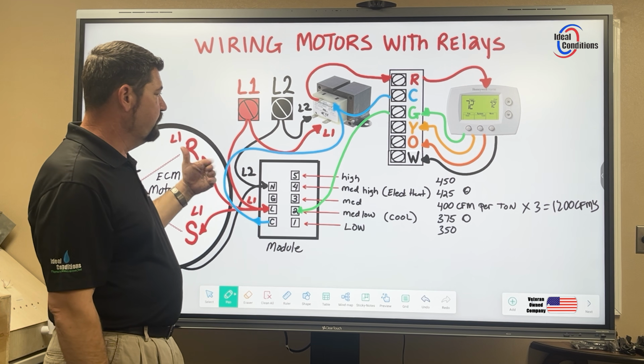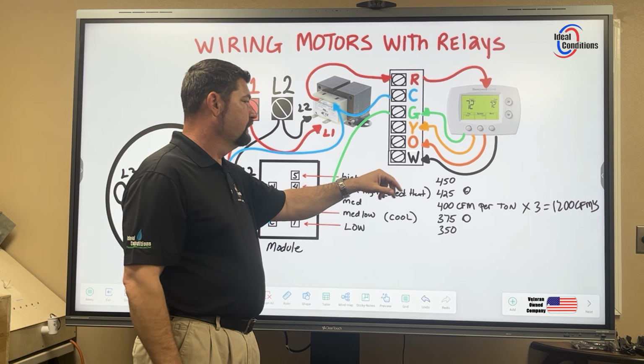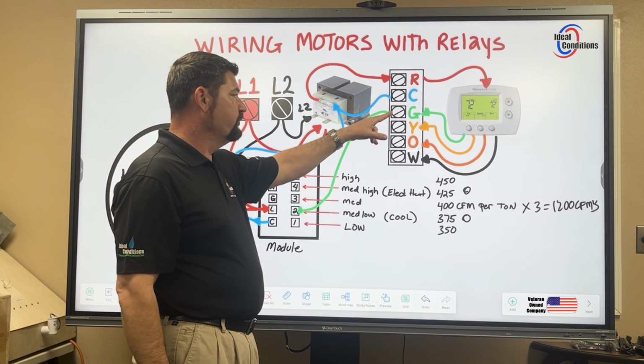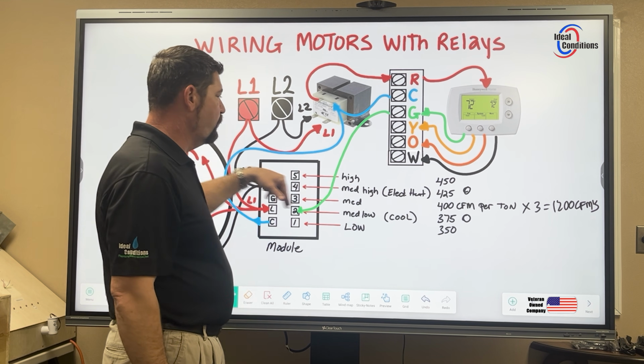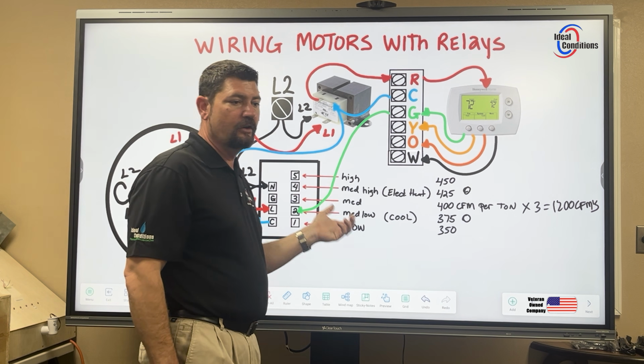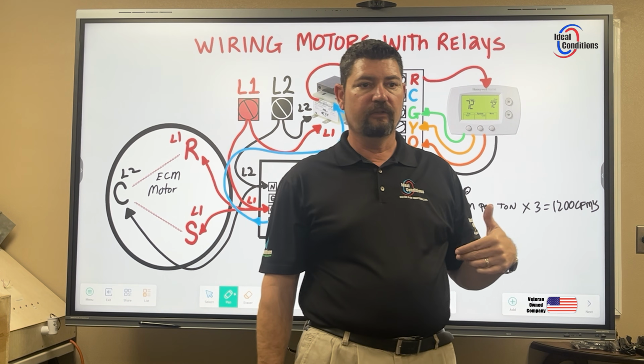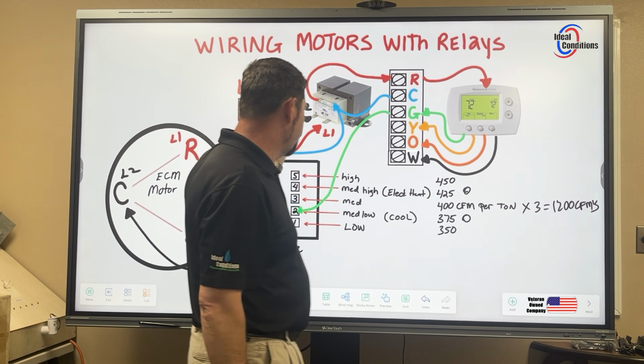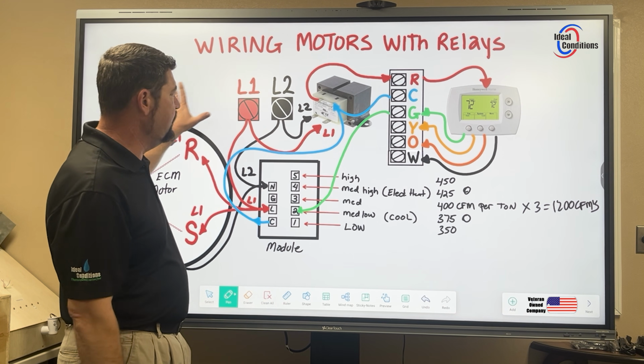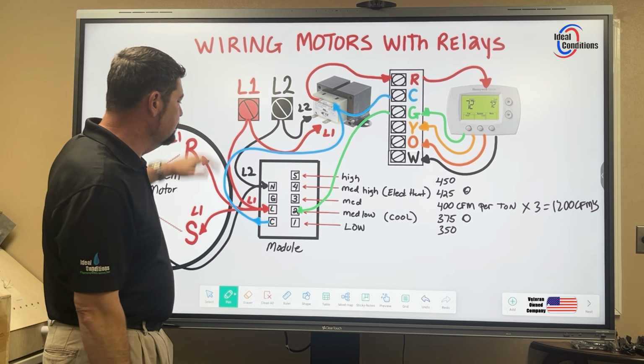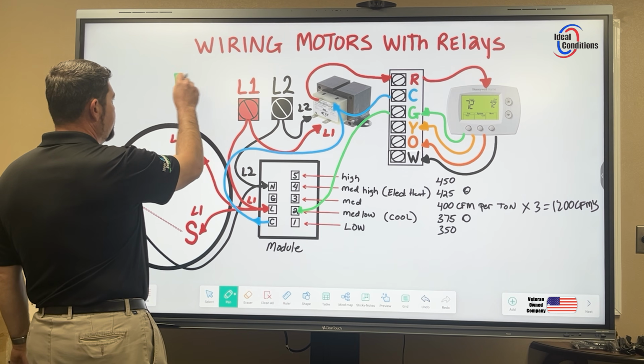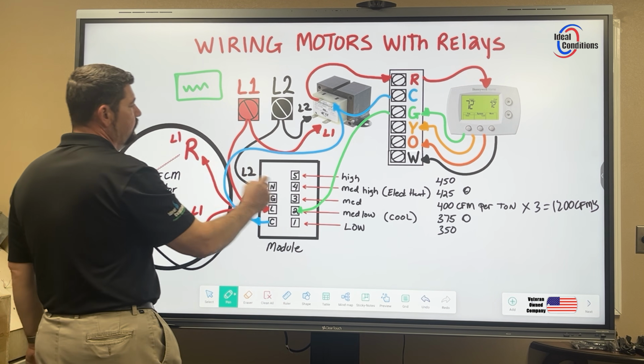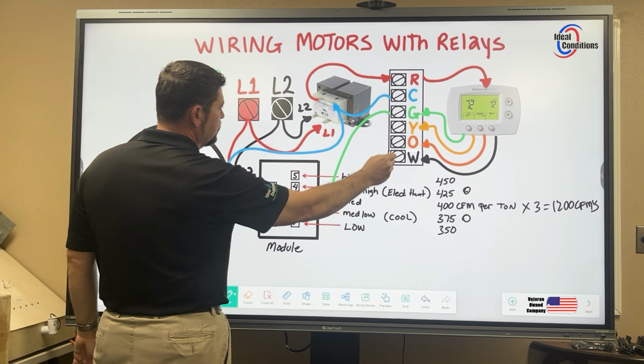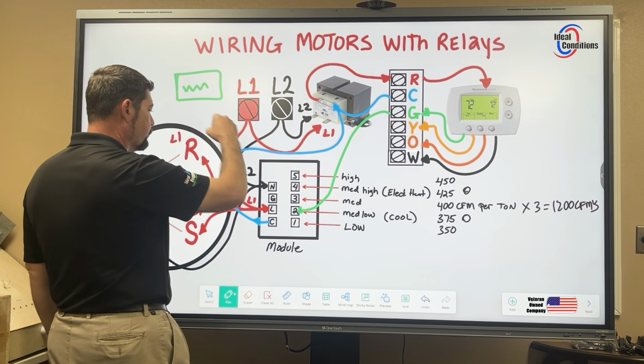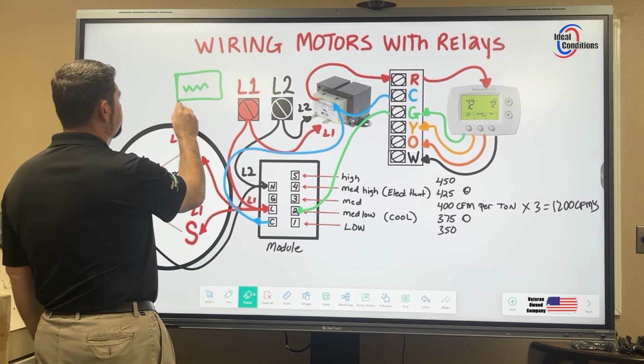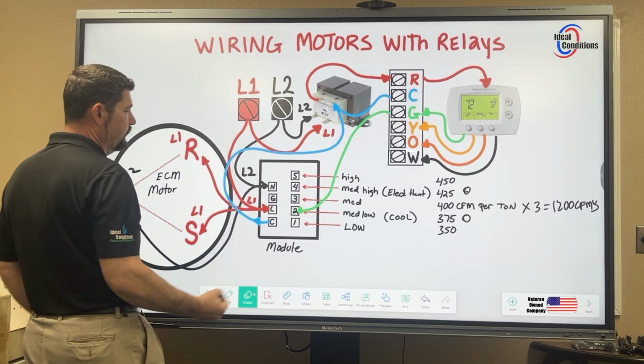So what they have done is they've actually taken the W, and if it's getting 24 volts, G's always there. They've taken that and they've wired that to your heat strips. And then also as a safety, if that relay ever sticks or if it's getting 24 volts, it comes back and it wires to terminal 4. Now I don't have a heating element up here, but if I did, simply I would say, here's my heating element, right? And I'm gonna run common and W up to it, and then out of here I would run back to 4. I'm gonna go ahead and erase that. And that's typically how that would be.